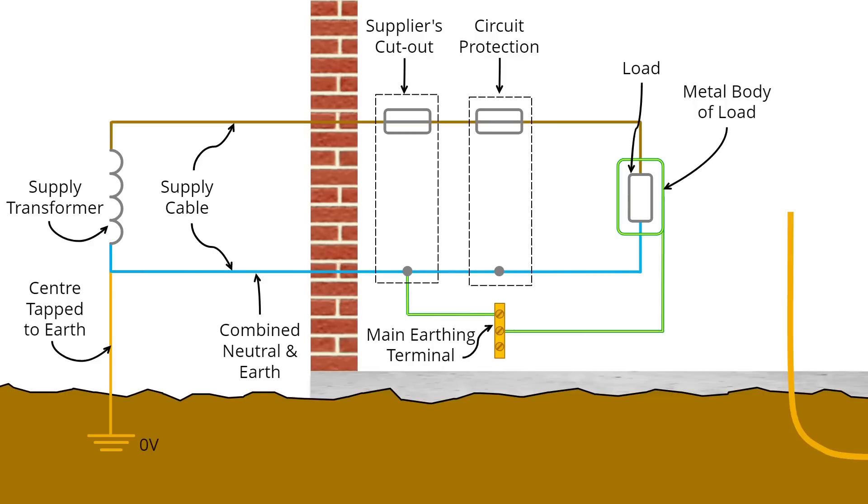If the combined neutral and earth cable supplying a house becomes disconnected outside the building, the current inside the installation will try to find ways back to the transformer supplying the property, and if someone's really unlucky and standing on the actual earth we walk around on or holding onto a metallic pipe buried in the ground, it could flow through them.